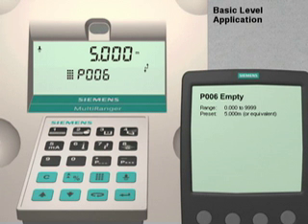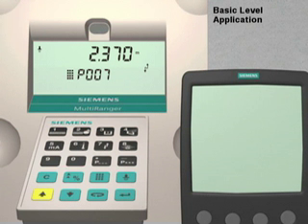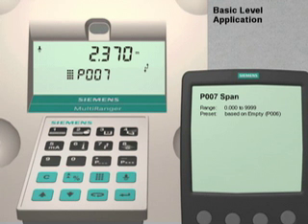Parameter 6 is the empty distance value. This distance is measured from the transducer face to the bottom of the vessel. For our application, this distance is 2.7 meters. To enter this value, press 2, decimal 7, and then the Enter key. Press the up arrow key to go to the final quick start parameter.